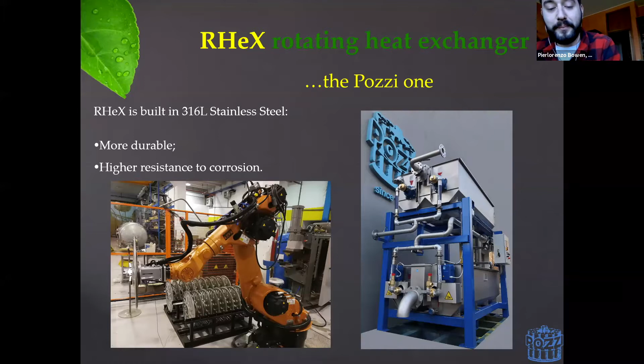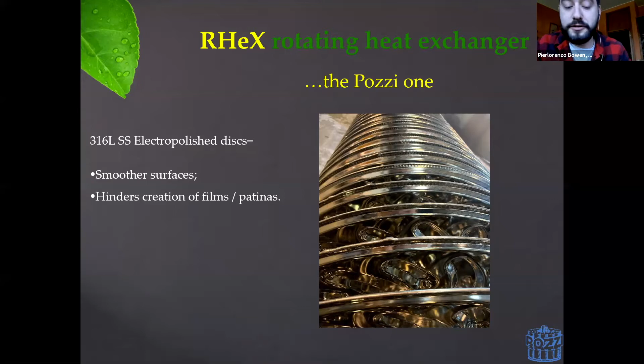Another thing that is worth noticing is that the rotor itself is electropolished. This is an electrochemical process which is done on stainless steel to effectively render the surfaces much smoother. This means that when you're dealing with chemical agents that would normally create patinas or films on the surfaces, you're actually rendering that much more difficult. The creation of patinas is almost impossible on well electropolished stainless steel.